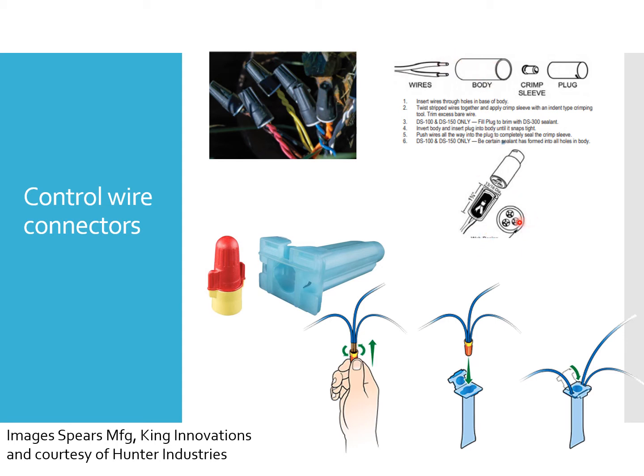You can see in this image right here that there's 3 holes. You would slide the wires through there, you would crimp them together, and then you would take that crimp with the wires in it and shove it inside of this plug and bring the plug inside of this body. So it sounds a little bit confusing, but by the time you're done with it, this piece and this piece have been put inside of this body. So now you've not only crimped the wires together, but you've also encapsulated them inside of a silicone filled plug. So once you've used this type of connection, you don't want to take it apart and try to reuse it, but this is a pretty foolproof way of doing it.